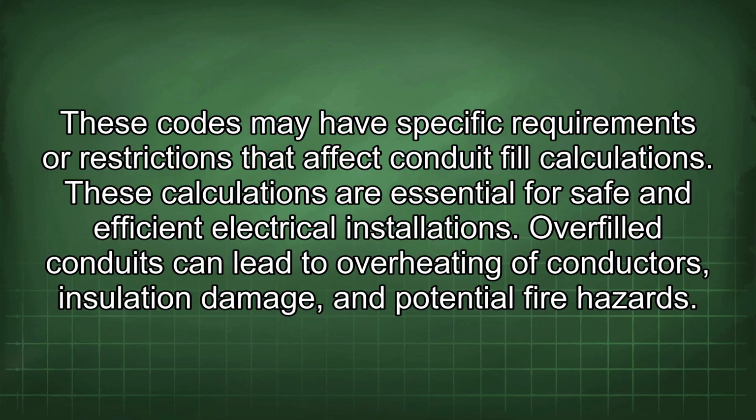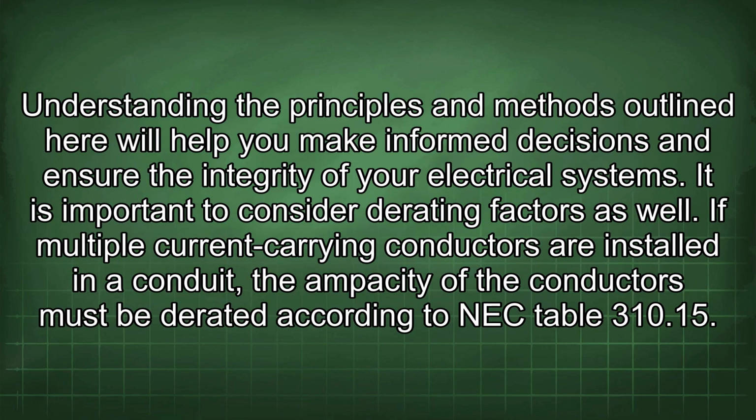Overfilled conduits can lead to overheating of conductors, insulation damage, and potential fire hazards. Understanding the principles and methods outlined here will help you make informed decisions and ensure the integrity of your electrical systems. It is important to consider derating factors as well.